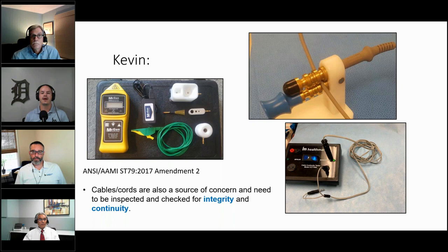But then on the lower right of your screen, you have the continuity tester, and this helps ensure the electrical wiring inside the insulation is also intact. Because these cords are often reusable and many don't even have an end-of-life requirement in the IFUs — some do, but many don't — there's a possibility the insulation could be great, but the metal wiring can be broken from wear and tear. When this happens, the electrical current may have to arc in order to get where it's going, and we don't want that happening inside our cord, because this can cause burning of the insulation. It could potentially cause a spark and a severing of that cautery cord while it's in use.